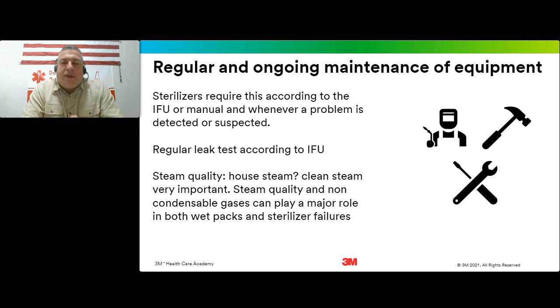There's steam traps, there's components that only have a certain amount of life cycle. They need to be replaced proactively, not after they fail. They could fail - your sterilizer might say replace the steam trap every 6 months, but it could fail in 3 months. It's hard when something is time-based because it depends on how busy your facility is. If something says replace every 6 months and you're a super busy facility, it might fail in 3 months. So that's why we want to make sure we have a robust, proactive maintenance plan in place for the sterilizers.